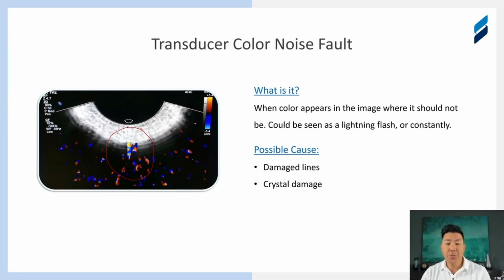So this is an issue, and this can be one of two main failures, not all of them. Again, it's all circuits. Anywhere in the circuit that breaks between the probe will cause these issues. So anything from a pin being bent and not having a proper connection to the crystal. But the most common failures here that you would see are damaged lines and crystals. And so, in this particular case, it could be one or the other. Doesn't mean it's not something else. Further diagnostics would be necessary at the component level. But again, something you should be looking for, and something that would require repair, and most definitely a repairable item.